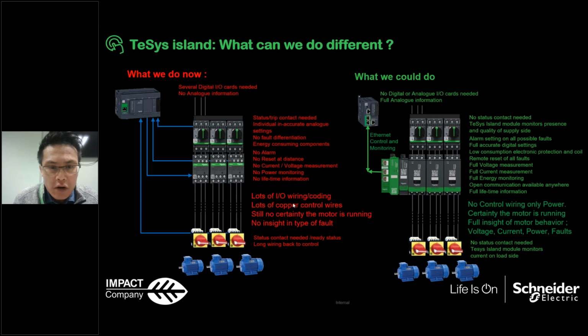So there is a lot of I/O wiring, a lot of control cabling, and this is what we do today. But what we could do to improve the system, to make it smarter or more intelligent, is to replace the existing contactors with the TeSys island, and then no status contact is needed. As I mentioned, no auxiliary contact block is needed because all the status is already in the bus coupler, and you can communicate to the system. We also monitor the presence and the quality of the supply side.